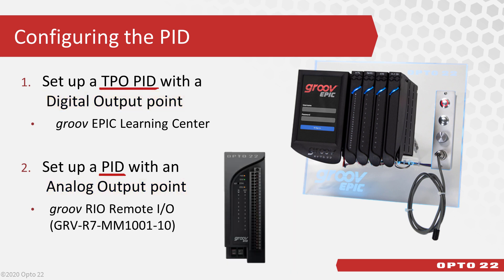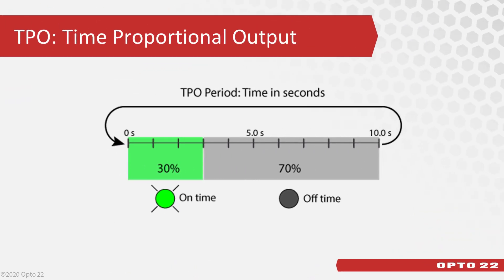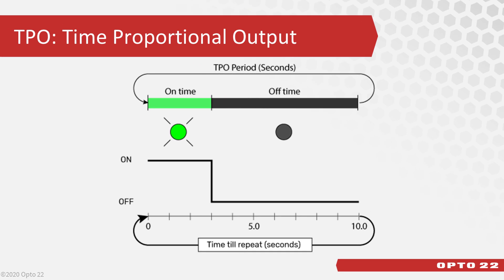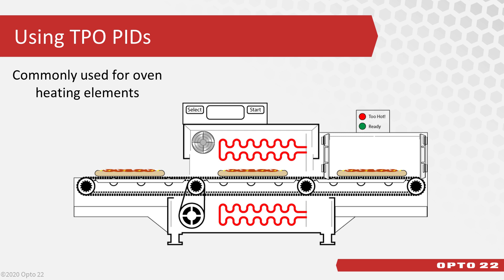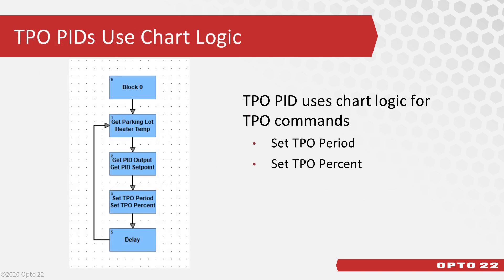Let's talk about these two types of PIDs a little more. TPO stands for Time Proportional Output — based on a period of time, what percentage of that time will it be on? You'll set up a period and a percentage for the TPO. For example, if your TPO's time period is set to 10 seconds and the TPO percentage is set to 30%, then the digital output point is turned on for 3 seconds and then turned off for 7 seconds. The TPO PID controls the digital output so that the temperature stays near the setpoint. TPO PIDs are very commonly used, especially to control a heating element like for an oven, or a solenoid to control flow or pressure.